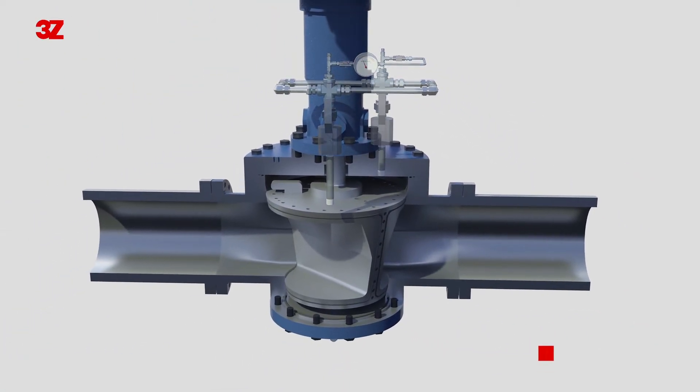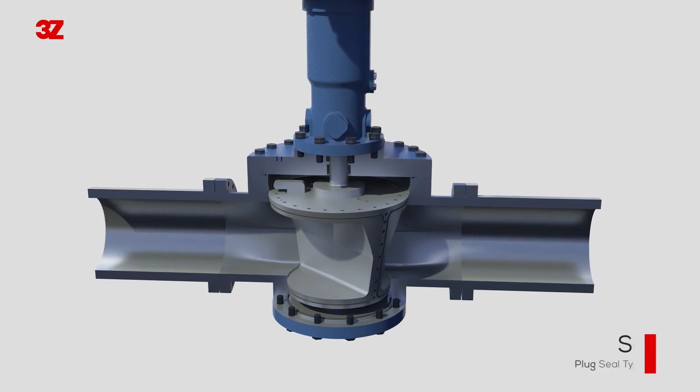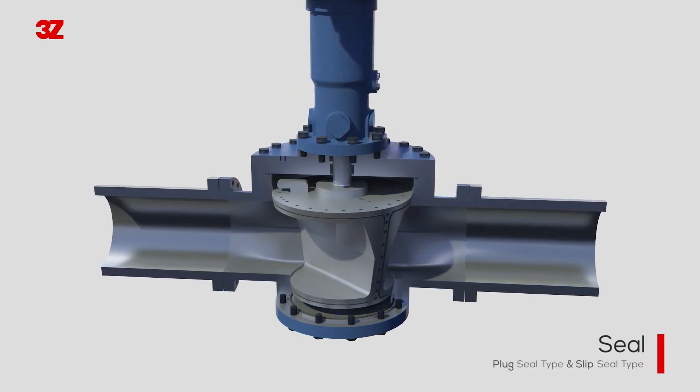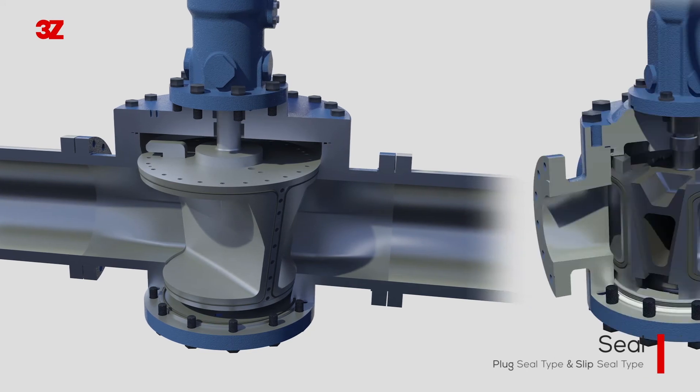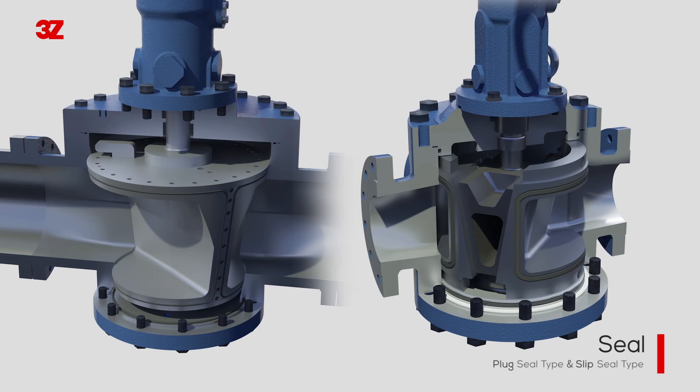The seal uses a soft material basically and we have two types of sealing systems. The plug seal type is attached directly to the plug for large sizes from 10 inches, and the slip seal type is attached to the slip for small valves below 10 inches.